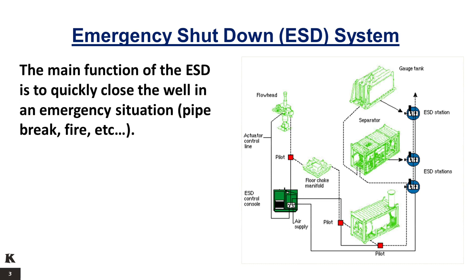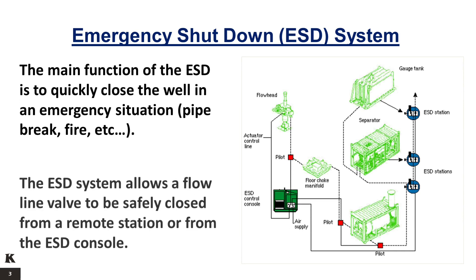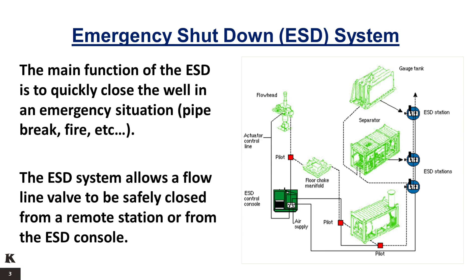The main function of the ESD is to quickly close the well in an emergency situation — pipe break, fire, etc. The ESD system allows a flowline valve to be safely closed from a remote station or from the ESD console. The well test emergency shutdown allows remote closing of a flowline valve should quick closure be necessary due to pipe leak or burst, separator malfunction, fire, etc. The system is suitable for connection to the actuated flow head valve or any other single-action, fail-safe, hydraulic actuated valve.